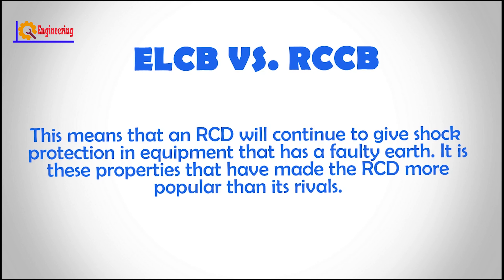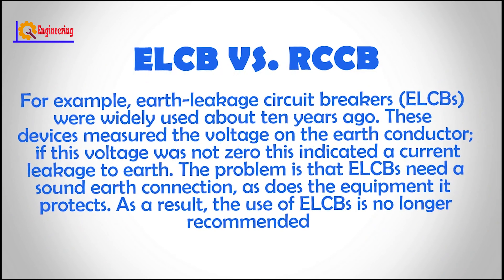This means that an RCD will continue to give shock protection in equipment that has a faulty earth. It is this property that may have made the RCD more popular than its rivals. For example, earth leakage circuit breakers, ELCBs, were widely used about 10 years ago. These devices measured the voltage on the earth conductor — if this voltage was not zero, this indicated a current leakage to earth. The problem is that ELCBs need a sound earth connection, as does the equipment it protects. As a result, the use of ELCBs is no longer recommended.